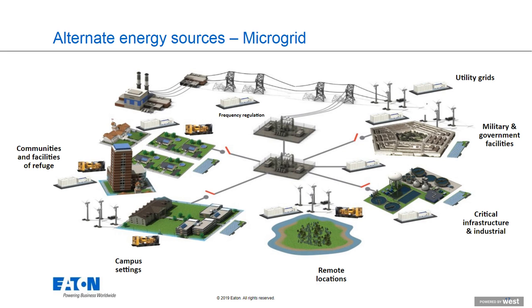So they'll utilize something called aggregation software, or an aggregator, that looks at all those UPSs together and decides who to draw energy from or who to ask to increase demand on the grid, doing that automatically so your enterprise functions as one big distributed energy resource made up of a lot of small UPSs, and maybe your generators out in the backyard, etc.